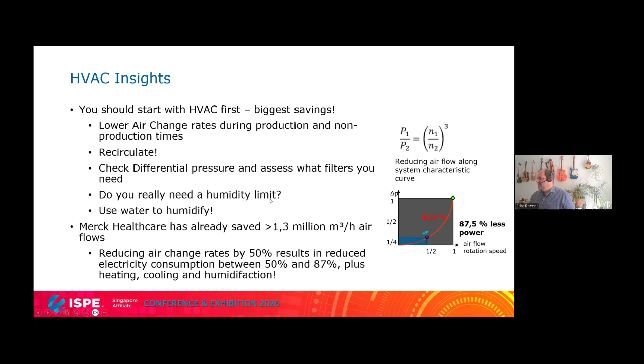And one more topic that is very interesting. You've got to understand the physics here. If you reduce airflows by half, then you need 87% less power per calculation. In reality, we see it's not 87, it's a bit less because there are pressure losses and you have old equipment and this and that. But the savings are higher than 50%. And in addition, the heating and cooling and humidifying that you would have done in advance is saved as well. It comes on top. So there is really a lot of savings in it and a lot you can do. We started 5, 6, 7 years ago, but we still invest time and money into HVAC topics because it's really worth it. We can still bring down air changes further.